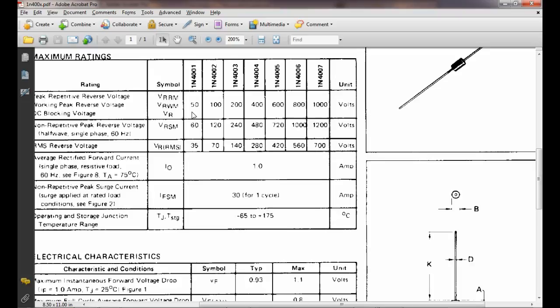This is another chart - you can find these charts. That was the MOV. On diodes, they're saying it's at least 20%, that doesn't mean you can't have more. And why they say at least, is because you might not be able to find an MOV rated at exactly 20%. So if you find one rated at 25 or 30%, that would be the one you choose.